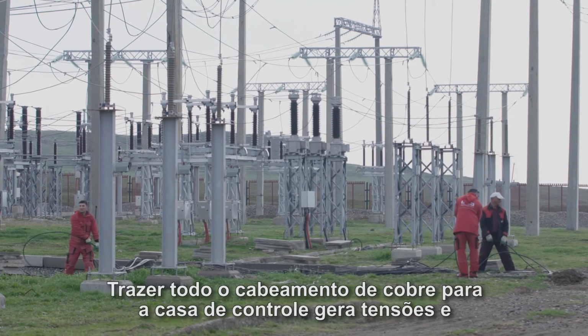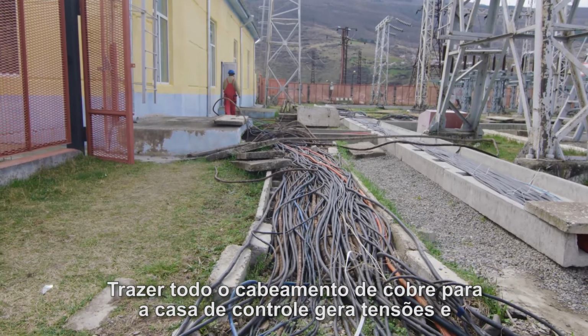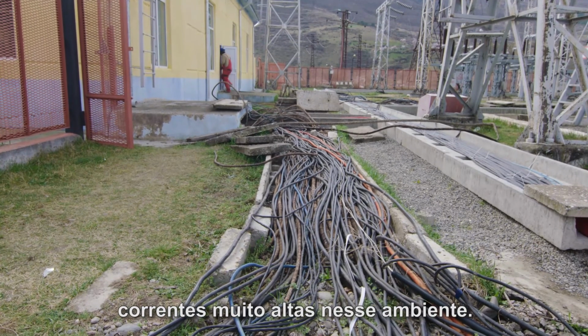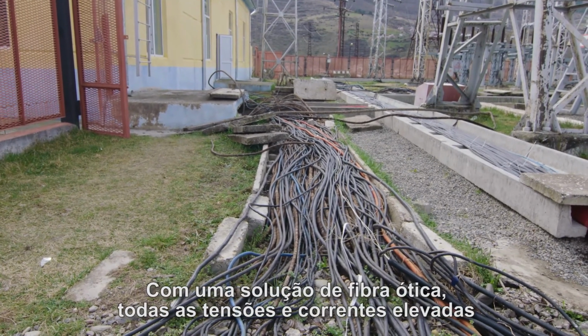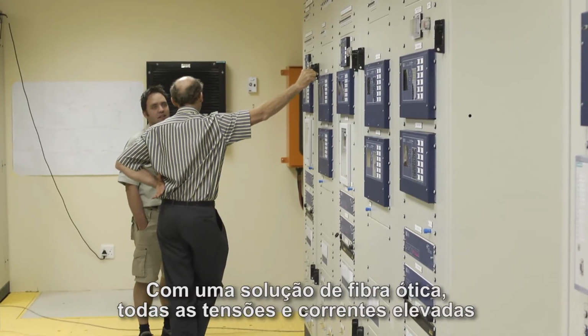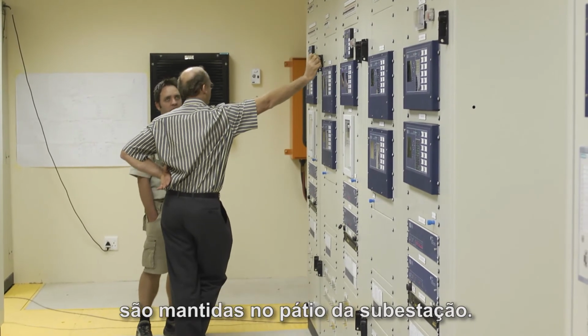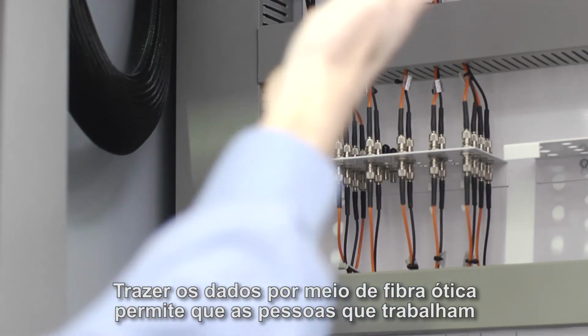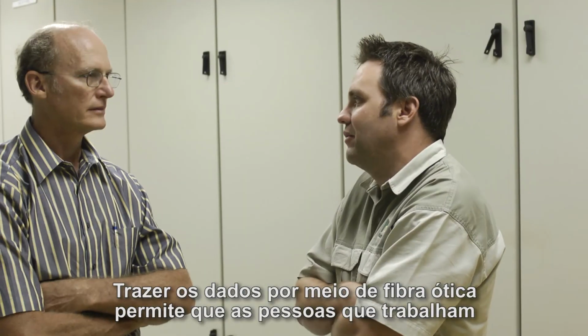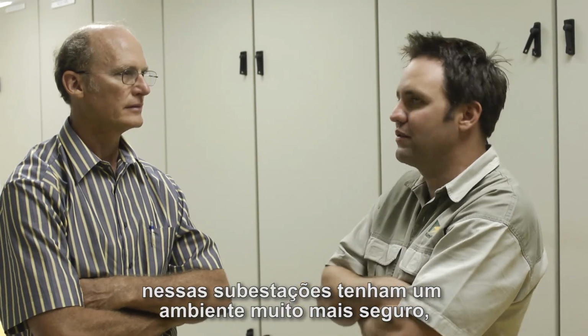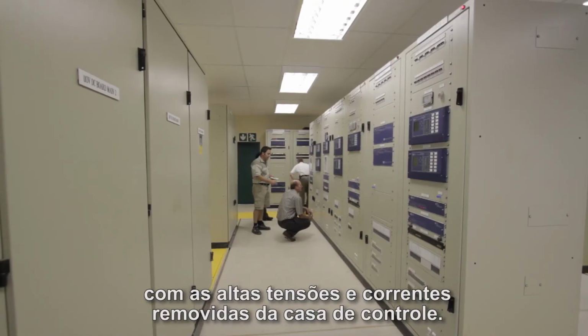When you're bringing in all that copper cabling, that represents very high voltages and currents that are now in the control house. When you go to a fiber optic solution, you keep all of those high voltages and currents out in the substation yard. You bring the data in over fiber optics. So the folks working in those substations now have a much safer environment with those high voltages and currents removed from the control house.